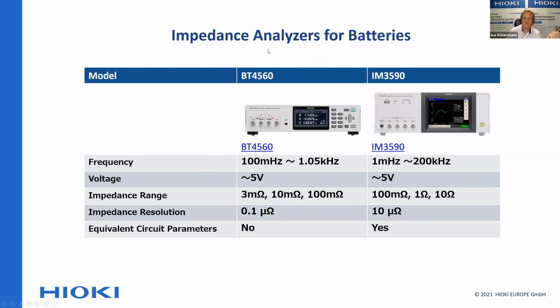Then we have impedance analyzers, and the impedance analyzer for a battery would be the typical instrument that you would use when you do the grading, when you do an EIS. We have two different types of these analyzers. One is the more classic one designed for lithium-ion batteries, the BT4560. It would typically be remote controlled with a computer, with the sweep controlled by the computer, while the IM3590, which is a chemical impedance analyzer, would even allow you to make these kinds of Nyquist plots on the screen.